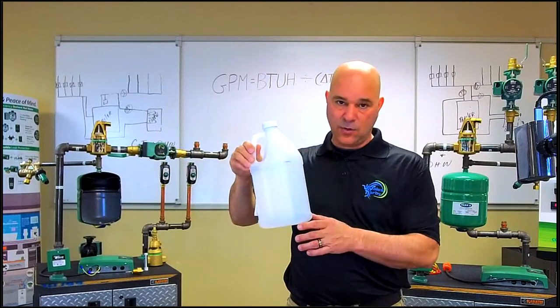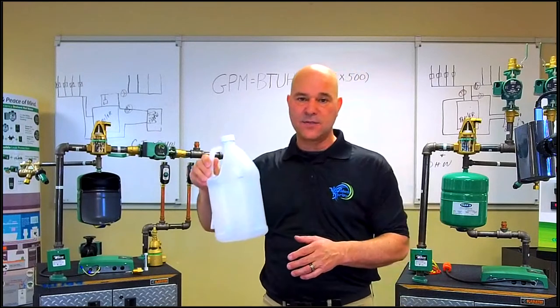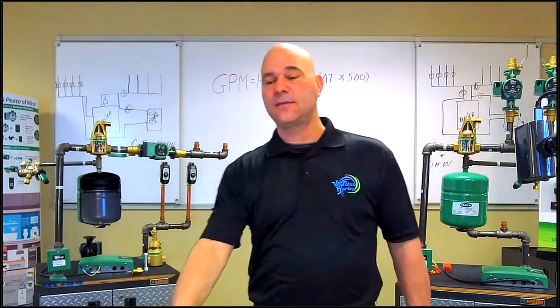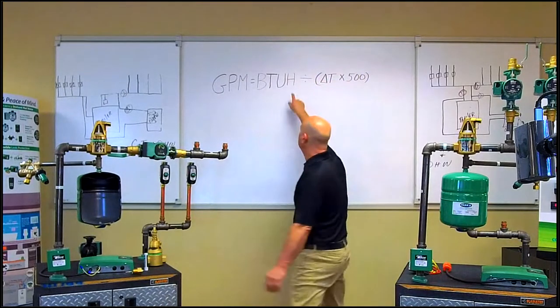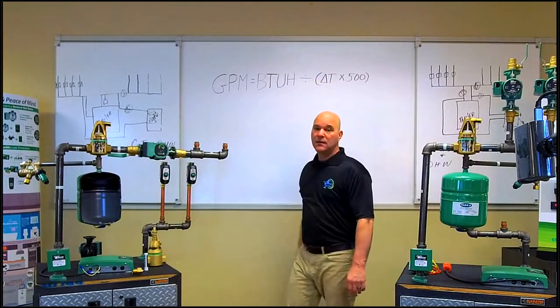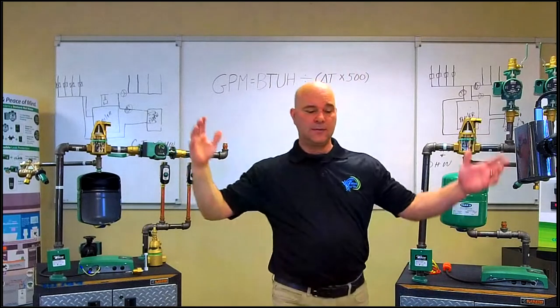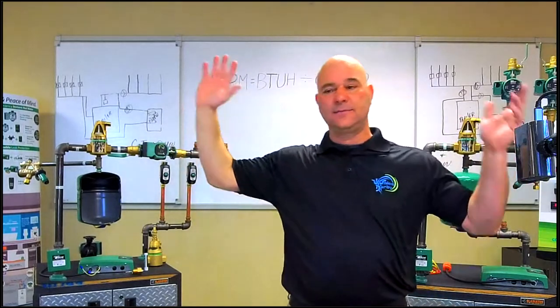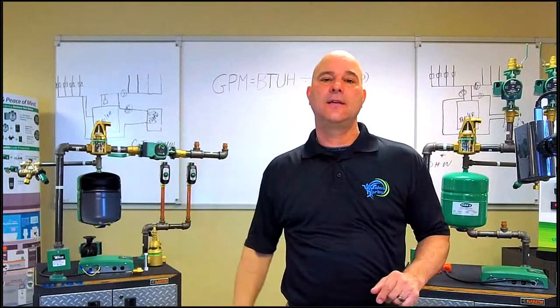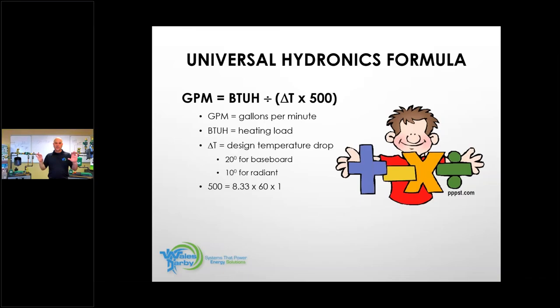If I take this gallon of water that weighs 8.33 pounds, and I multiply that by 60 minutes, the hour, that will give me like 498. We round it to 500. So what we're saying is that this gallon of water that weighs 8.33 pounds over 1 hour equals 500.